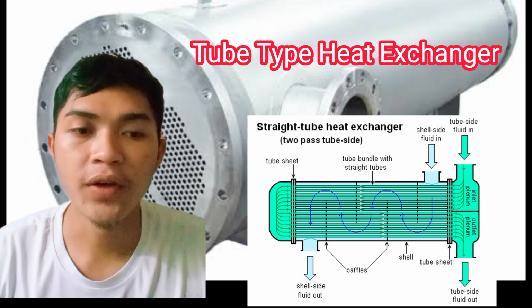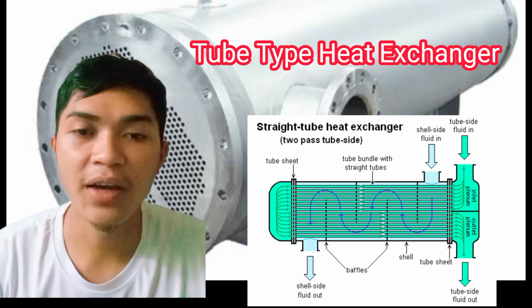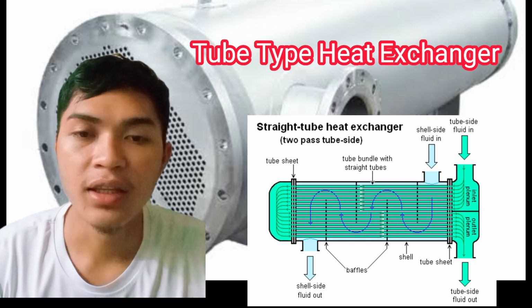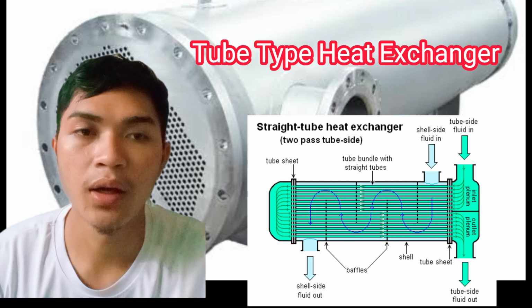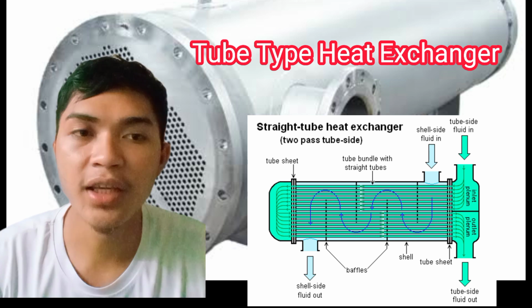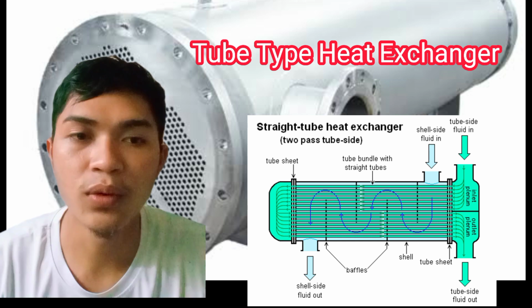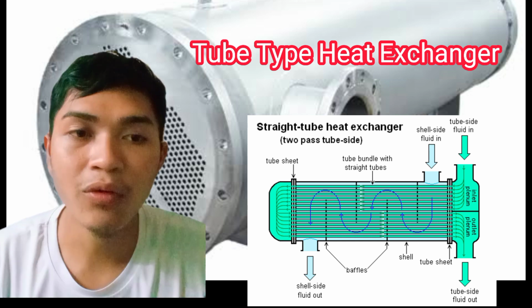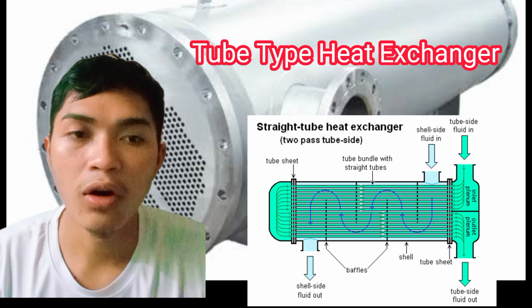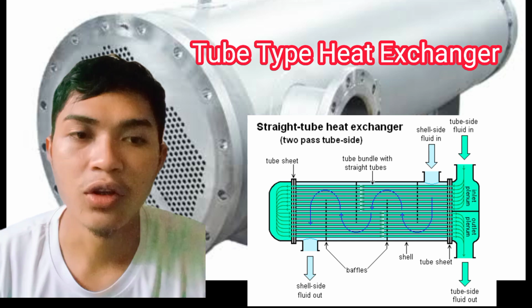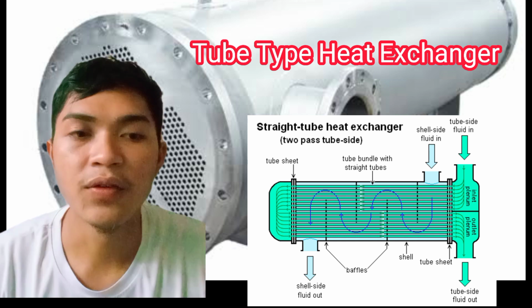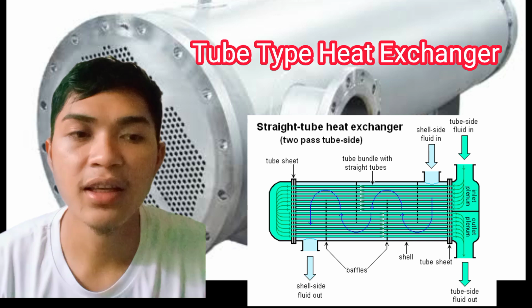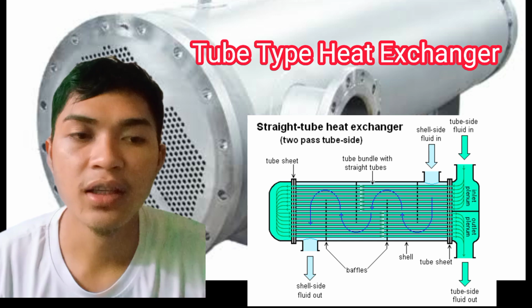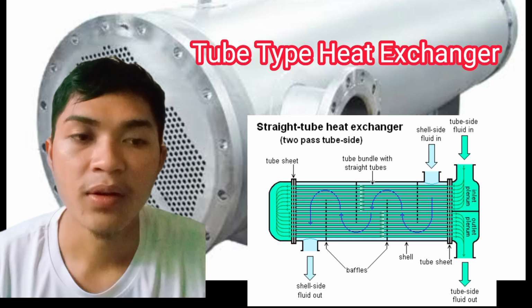If it's a shell and tube type heat exchanger, leaks can be detected by following the procedure below. Isolate the heat exchanger from the system and drain the seawater. Remove the end covers or headers to expose the tubes or plates. If the surface is clean and dry, inspection of the liquid flow is made from around the tube ends and through the perforations.